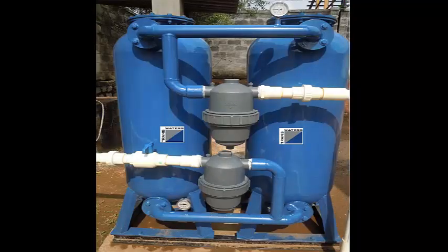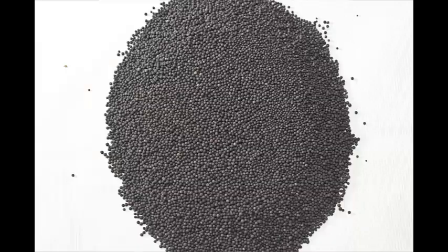If you only have two cylinders, one could be a multi-grade filter and the other a softener. People mix sand and carbon in the first cylinder, put in stage by stage based on grading, and the second one can be the softener. If you have iron, people have an additional cylinder to remove dissolved iron from the water, using different manganese dioxide based material to treat iron. So if you live in an apartment complex, you have multiple stage cylinders.